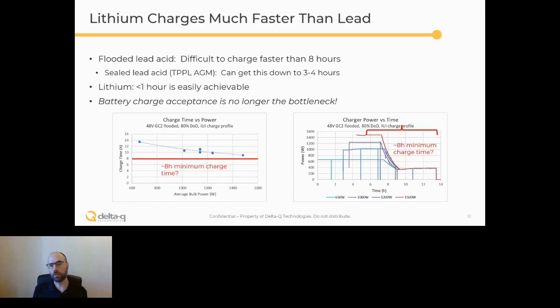As you push the current and the voltage higher above the gassing voltage, you'll gas more vigorously, you'll generate more heat, the battery will lose more water. And if you decrease the charge return factor below that 110% that a flooded battery needs, you don't fully convert all the lead sulfate, and you can have permanent loss of capacity and shortened battery life. So really, it's possible to charge lead acid faster, but there are definitely diminishing returns with what's achievable in terms of maintenance and battery life.